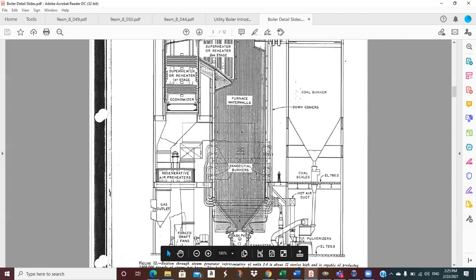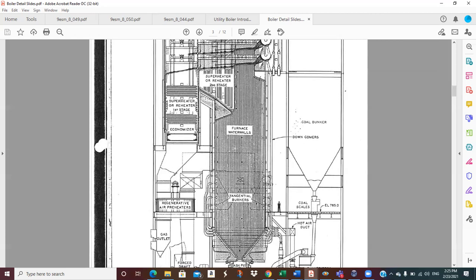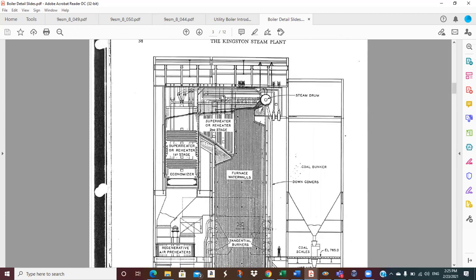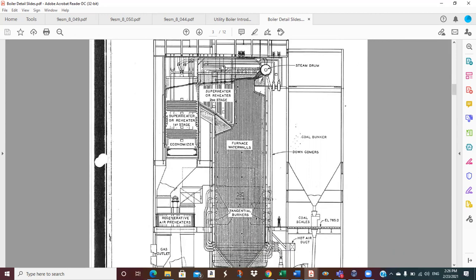So this is a T-fired boiler, so these burners are in the corners of the boiler instead of the walls. There's your furnace water walls that are generating your steam. It goes to the steam drum and then comes over through all the superheaters like we talked about, economizer, air preheater, rather.